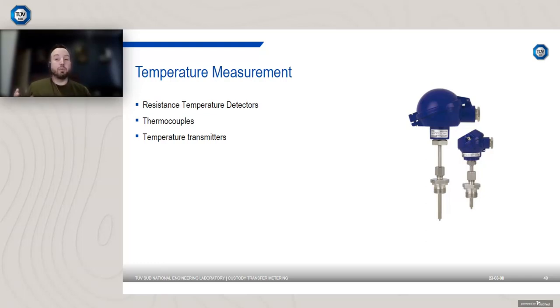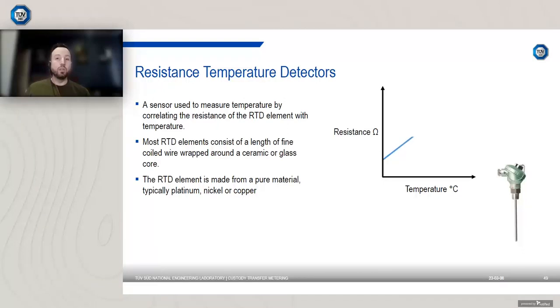There's different methods for temperature measurement. I'm just going to focus on resistance temperature detectors in this webinar. So how does a resistance temperature detector work? Well, it works by measuring changes in electrical resistance of some form of metal element. So usually platinum is the most popular material, but it can be nickel or copper. Why is platinum so popular? Well, it's fairly stable, and more importantly, the resistance to temperature relationship is fairly linear. So you can characterize that relatively easily. So by measuring the resistance of the element, you can then relate that to temperature.